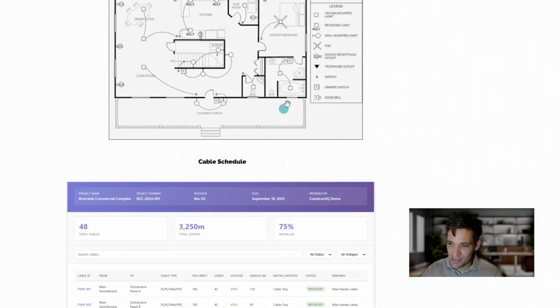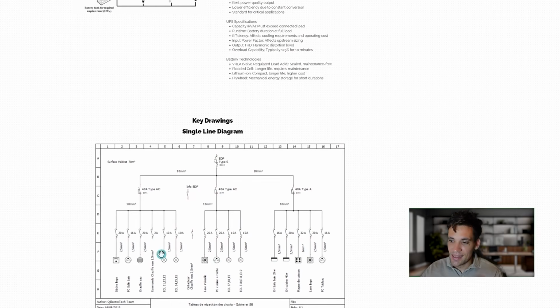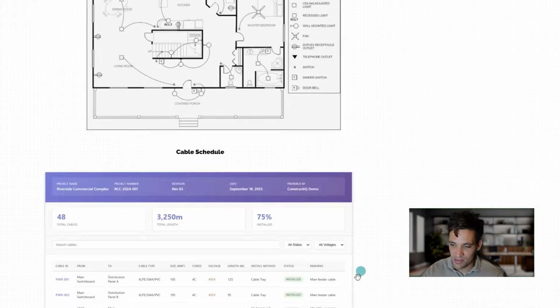Again, when understanding these components, it's also essential to understand the principles of protection coordination. What this pretty much means, and I've spoken about this already, is that when you have a fault on a load, like one of these devices here, this circuit breaker should operate before this circuit breaker. It's purely done because if you get a fault on this and this breaker trips before that breaker, you lose power to the whole system instead of just losing power to this system.